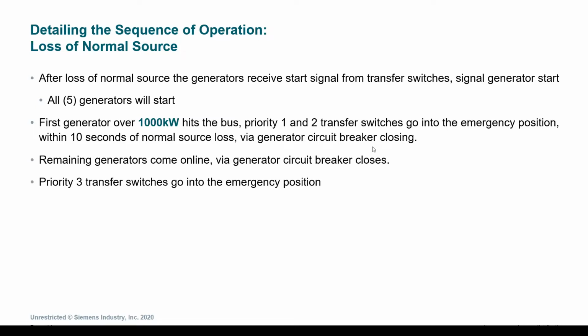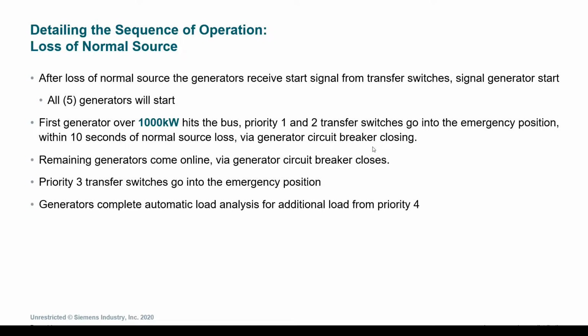From here, the priority 3 transfer switches go into the emergency position and are being energized. At this time, the generators complete an automatic load analysis for the additional load from priority 4 to come online. Although in our assessment on the previous slide, we showed that the generator capacity can support this, the system wants to evaluate that all the generators are online and that capacity is available, that nothing is down from a failure or from maintenance.